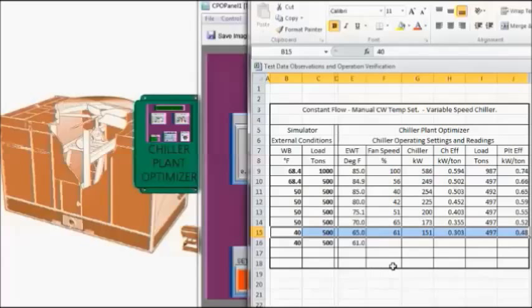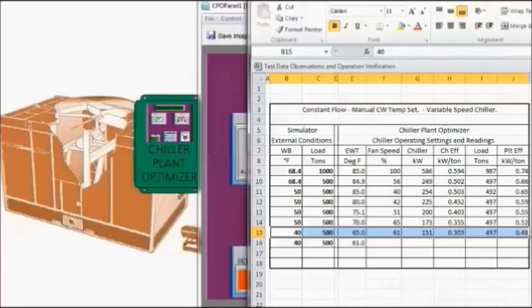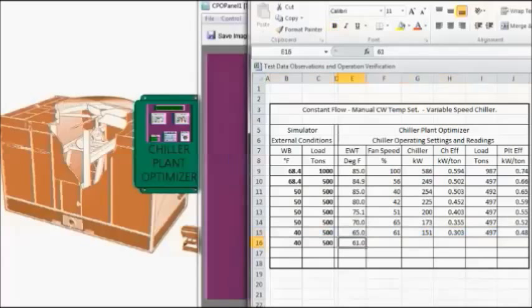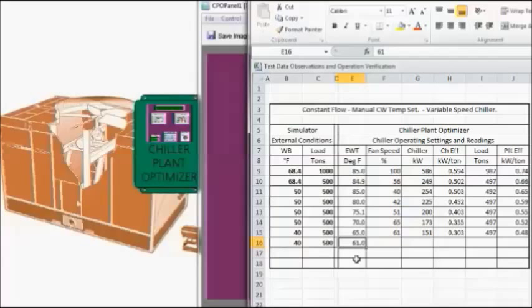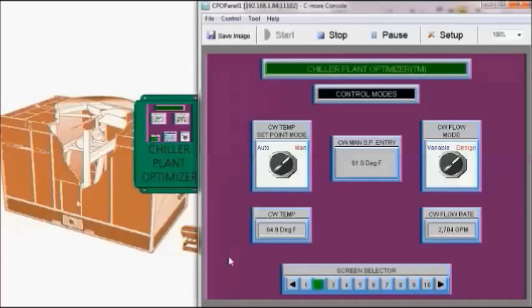So fan speed dropped to 61%, chiller efficiency down to 0.303 kW per ton, still at 497 tons of load, and we're down to a 0.48 plant efficiency. So now we're going to enter the temperature set point at 61 degrees Fahrenheit.